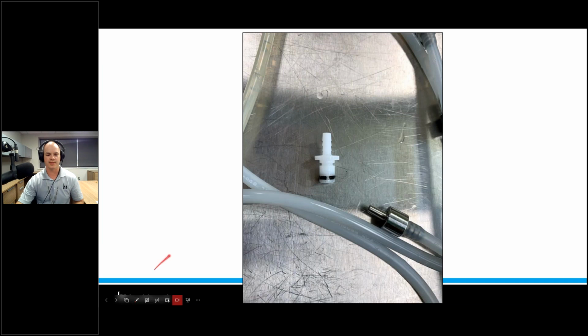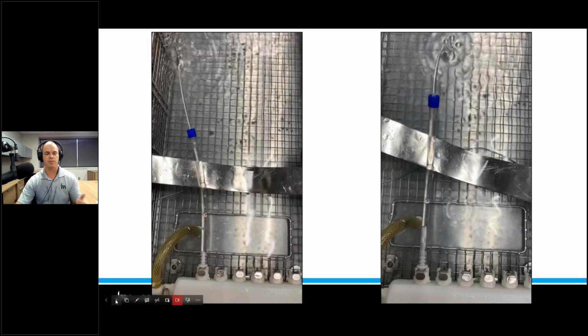So what happened to that one on the top left? Well, the broken O-ring underneath was the problem. So if you see that, I think maybe just because it's such a small component or small part, people don't generally look for this. I go around to departments all the time and I see broken O-rings on these accessories a lot. All right, they get used a lot and they break down over time. They do need to be replaced, but if you're not convinced that a broken O-ring can really be a problematic issue for your cleaning process, that's what I put this in here for.